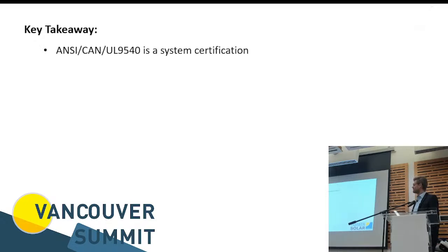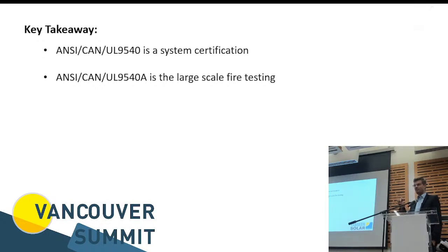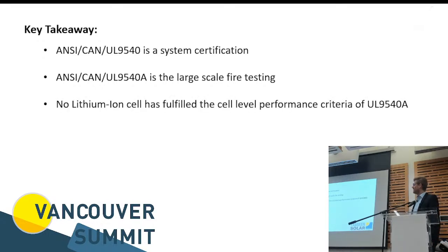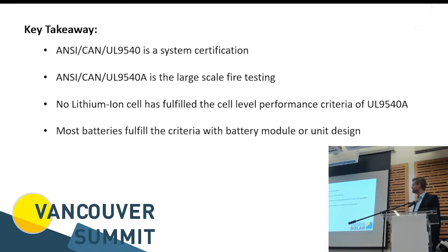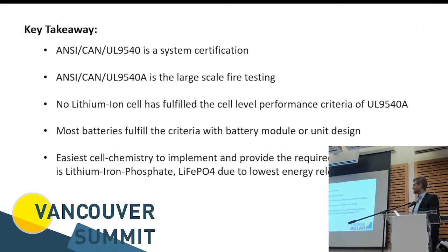The key takeaway is that UL 9540 is a system certification. The 9540A is the underlying fire testing. And unfortunately, there's no lithium-ion chemistry cell that fulfills those very hard fire and performance criteria of the UL 9540A as written in the code right now. And most battery systems, as already said, pass by putting multiple cells in a module and then multiple modules in a system. And the easiest chemistry is lithium iron phosphate because it's the lowest energy release in the thermal runaway.